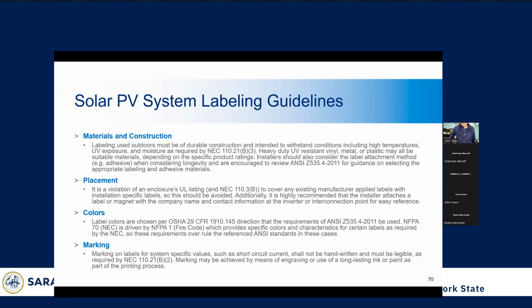All right, so within the New York State solar guidebook, you'll find a detailed labeling guide. Labeling can be very challenging, even for experienced contractors. Things to remember are labels have to be durable. They're supposed to last 25 plus years. They should be placed in manufacturer recommended areas, not covering other labels, of course. Colors are predetermined by ANSI and OSHA, so they have to have the correct coloring. So typically for solar PV systems, they'll be yellow, orange, or red. So if you see a different color label, it's probably wrong.